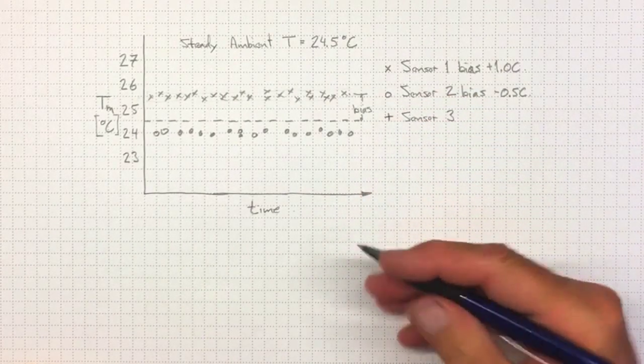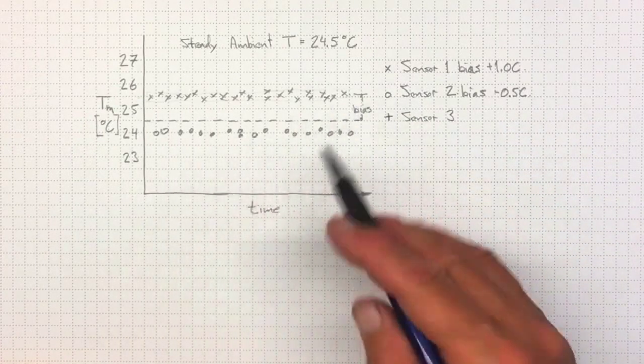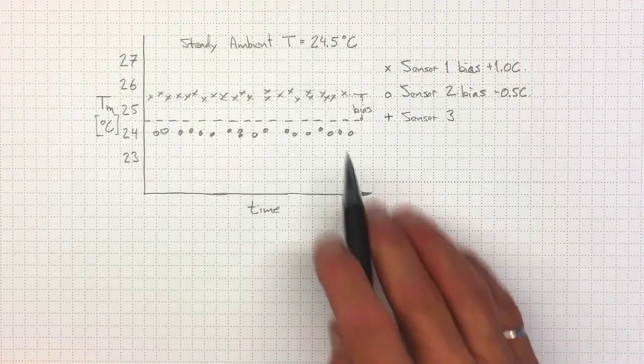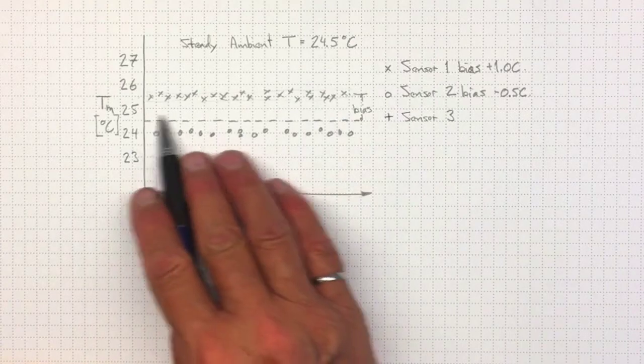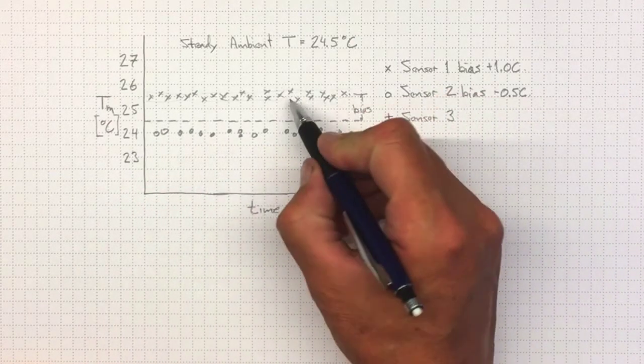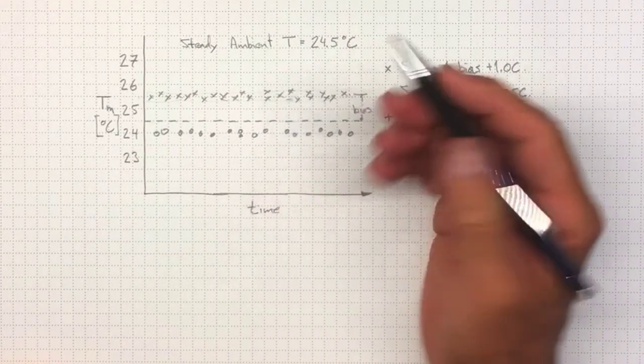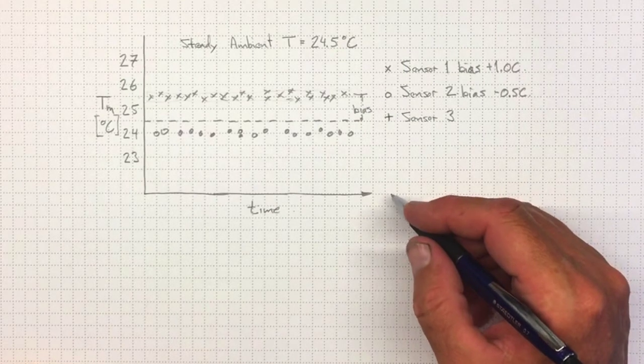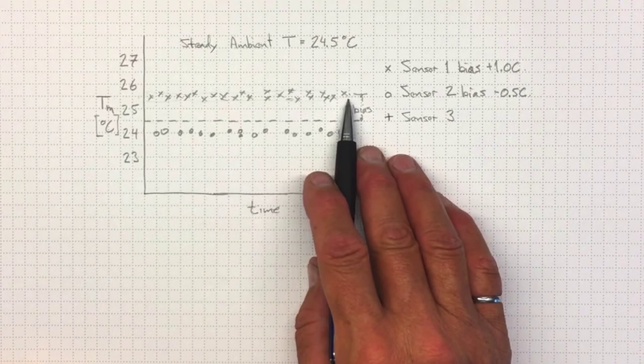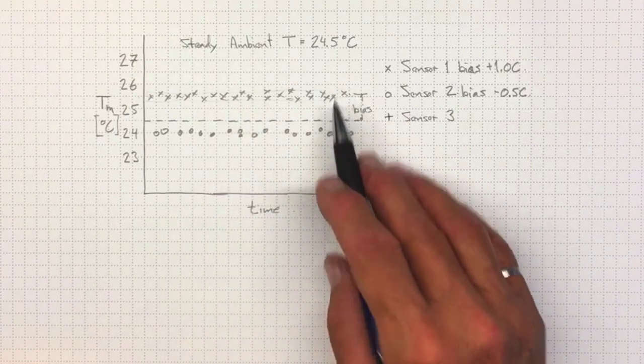That's expensive. That requires some trained personnel to go and actually make that test measurement and to make it again later on because you need to keep this calibration up to date. So that's a little more difficult. It takes extra work, so it's going to cost extra money. But if we did that, we could find that maybe the standard deviation on here is maybe 0.2. So two standard deviations would give us an uncertainty of maybe 0.4 degrees Celsius instead of the considerably larger uncertainty.